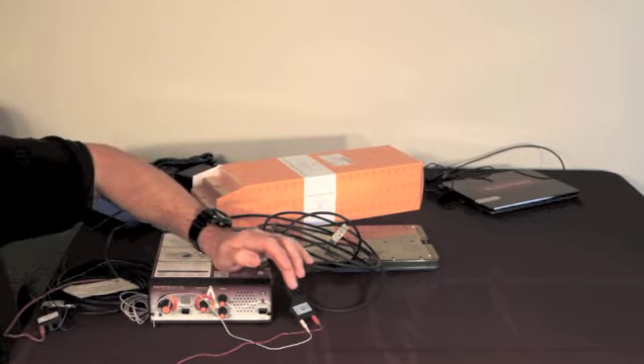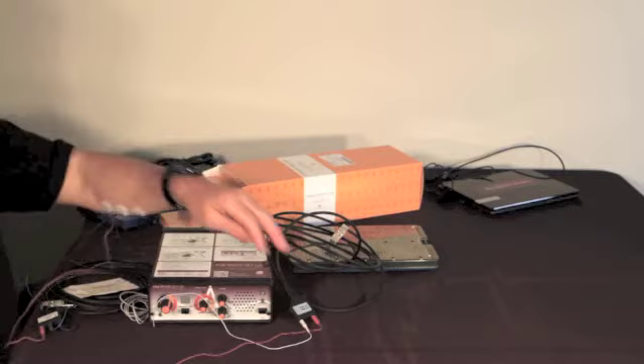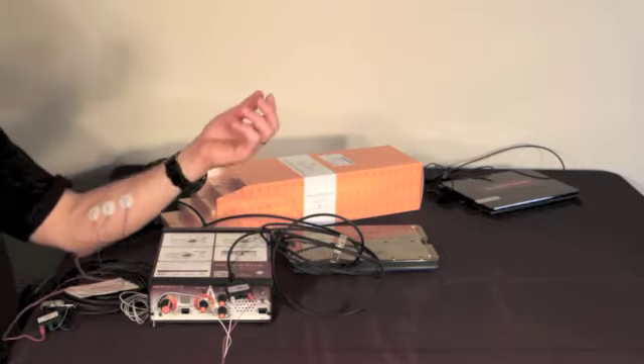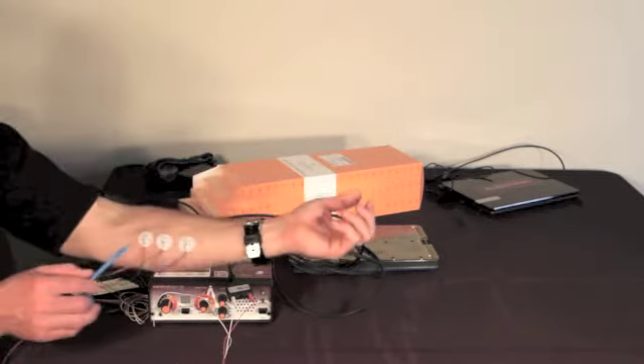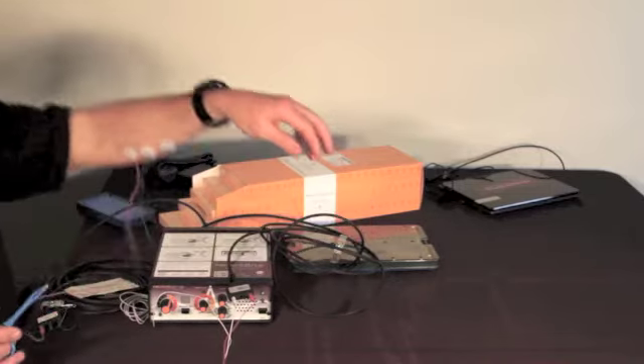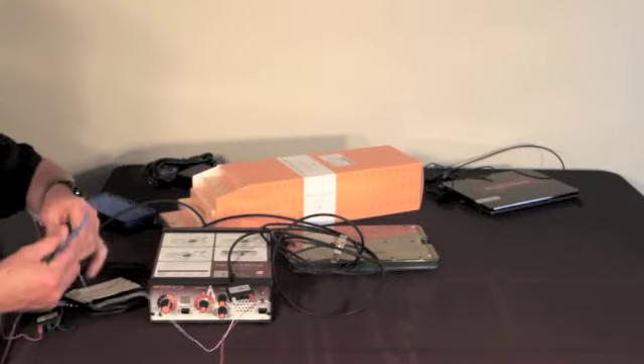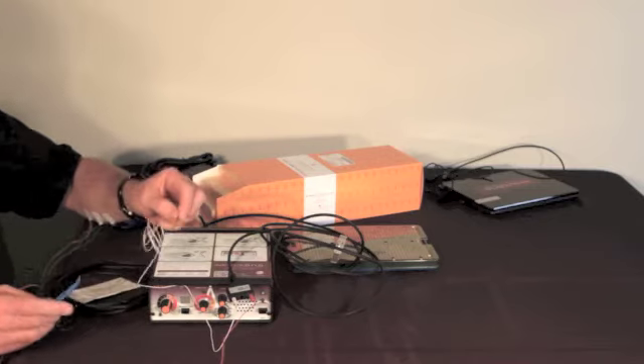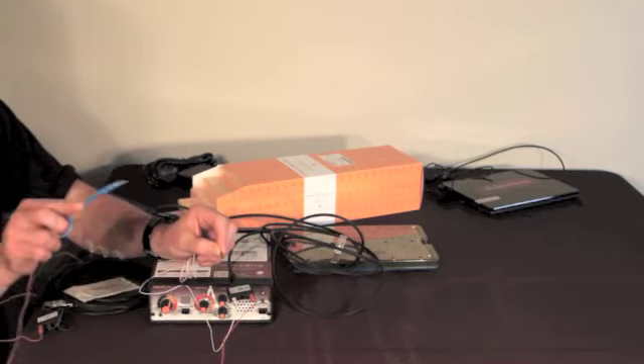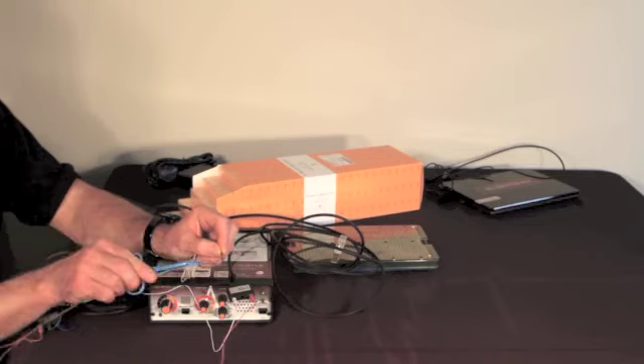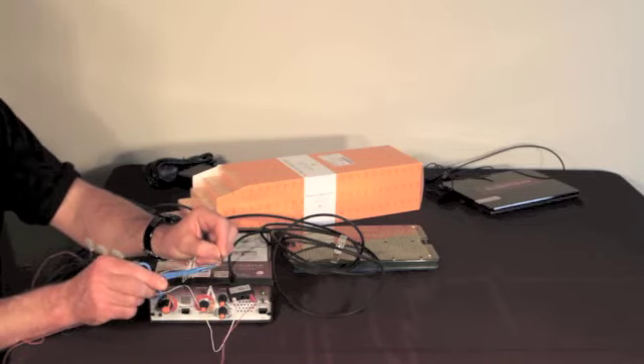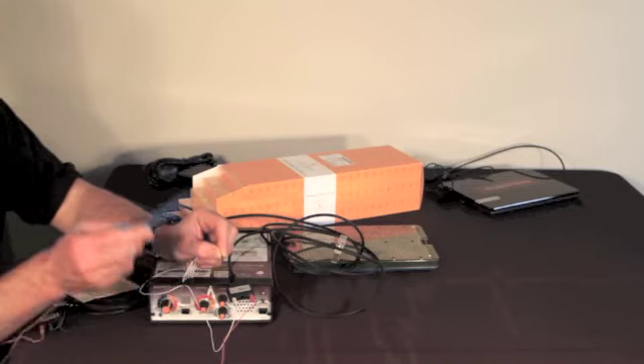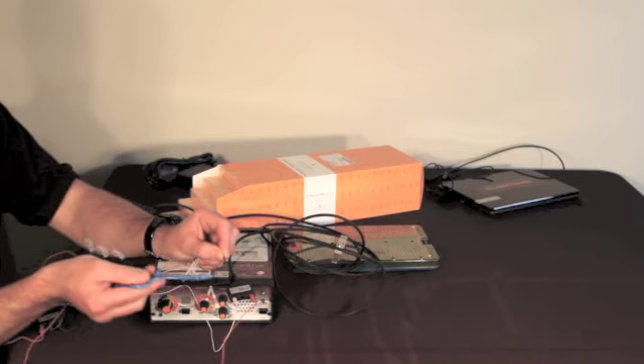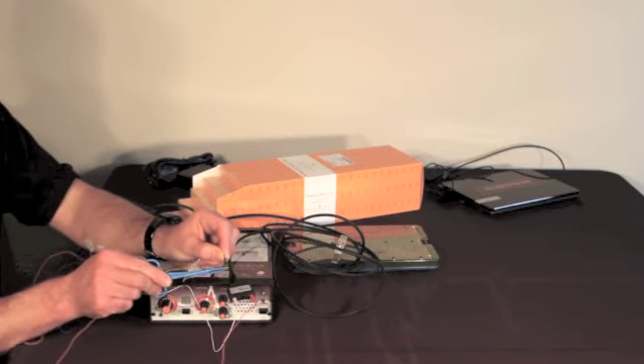verification of the connection is possible by touching the patient and testing that stimulation is being delivered. And I'm gonna show you what that sounds like. If the needle return is in the patient and you touch them somewhere, the current is going to pass back to the needle. I'm going to short circuit the patient by just showing you a direct path. So that clicking, ticking sound verifies that your probe is delivering stimulation to the patient. One more time.